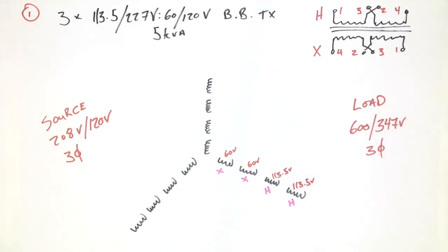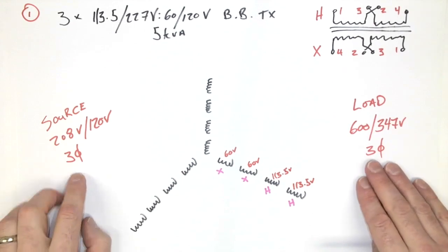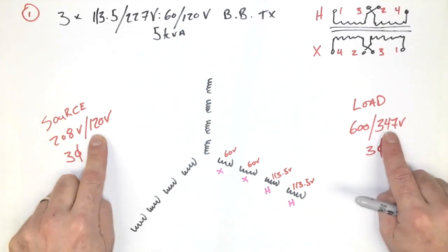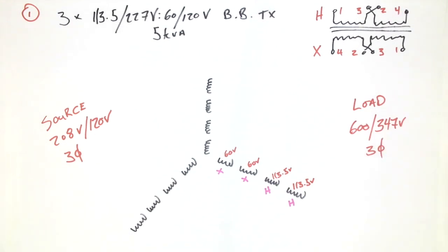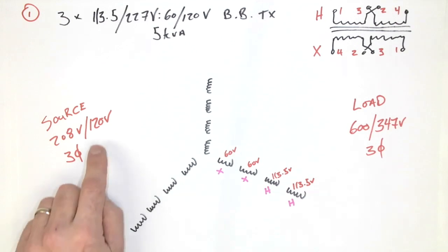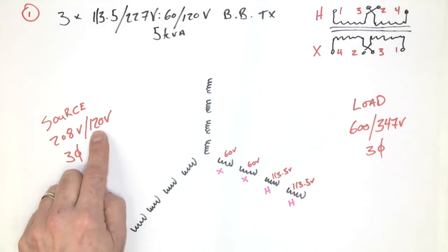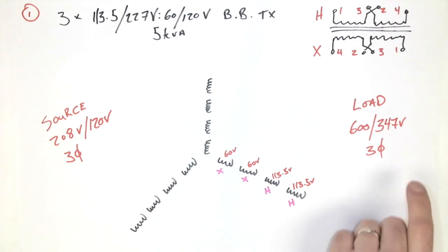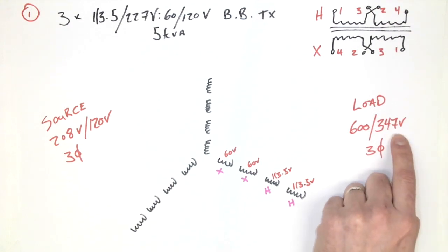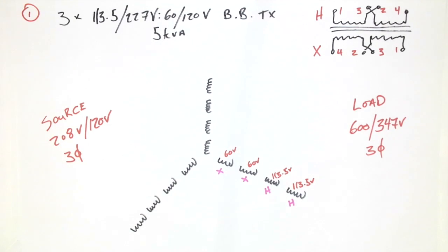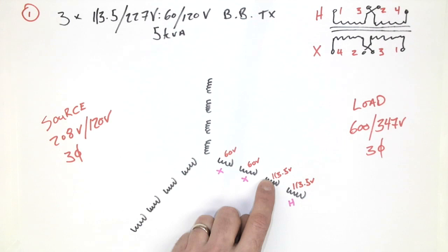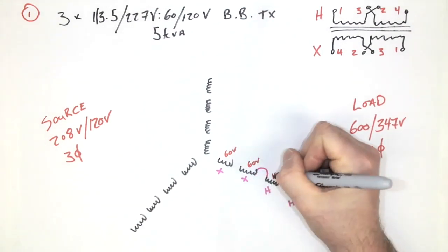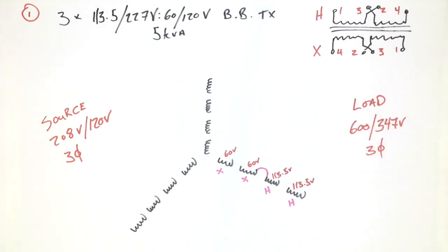What we want to do is connect this source to service the load, but remember it's a Y connection, which means I really only need to know the phase voltage values. The first thing we should be aware of is that the phase voltage of 120 needs to be present as well as a phase voltage of 347. Now, with this particular installation, we know that since it's an autotransformer, the X and H windings are going to have to connect together in series. So I'm just going to put that in here because it's kind of a foregone conclusion. It needs to be there.